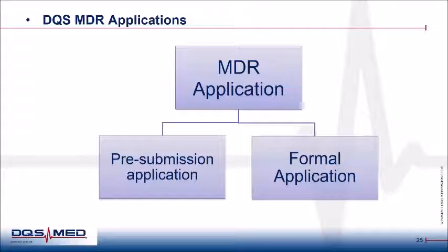and make it very clear that the technical aspects of the medical device have to be evaluated to a far greater extent than was required under the Medical Device Directive, which means that we have to check for the availability of the technical file very upfront. So the technical file has to be filed in with the actual application itself. And the next thing is the result of the evaluation, especially if it has to be rejected for whatever reason, has to be also forwarded to this Eudamed database and is then available to the European authorities and potentially also to other notified bodies.